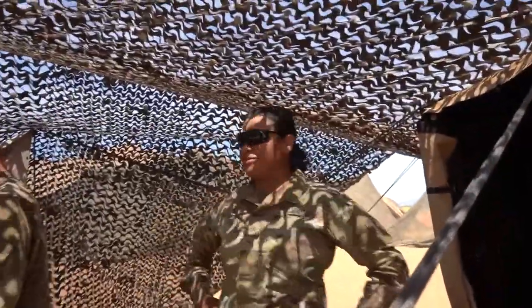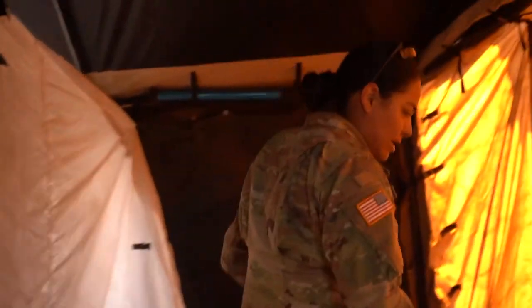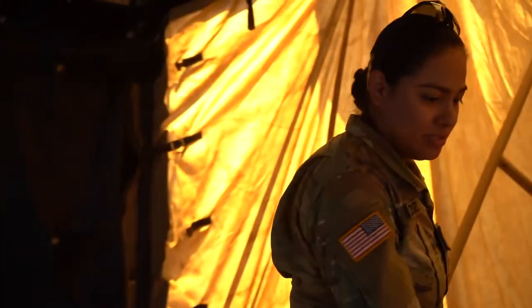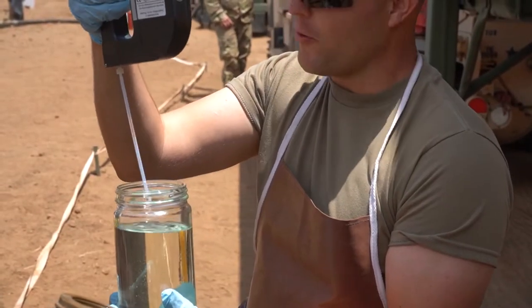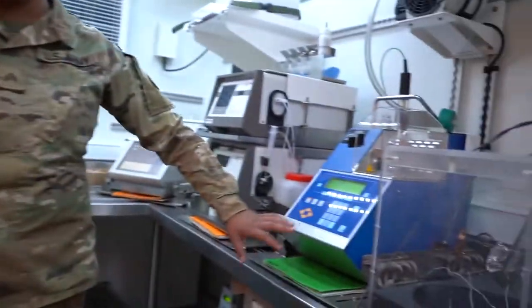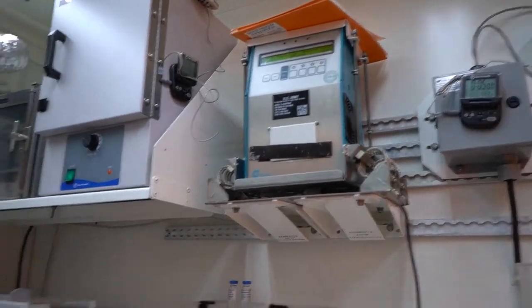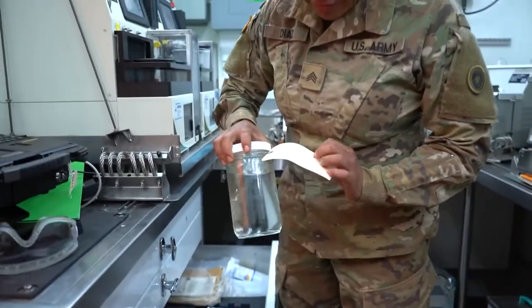We're trying to get our samples from the trucks. Salina Diaz with the 306th Quartermaster Company — I'm a petroleum laboratory specialist. Once we get the samples inside the lab, the first thing we do is our API gravity, which gets us density, API, and temperature. Then we start running the different types of tests: distillation, flash point, density, and freeze point.